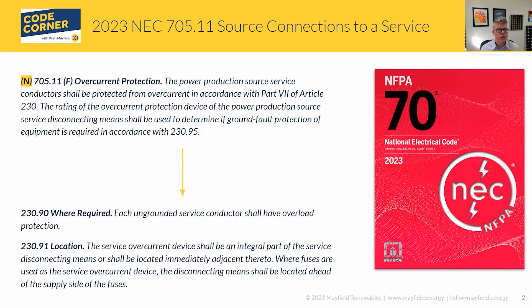The 2023 language says power production source service conductors shall be protected with overcurrent in accordance with Part 7 of Article 230. It also goes on to talk about ground fault protection depending on ampacity, referencing 230.95. Part 7 of Article 230 is service equipment overcurrent protection, covering sections 230.90 to 230.95, at the very end of Article 230.